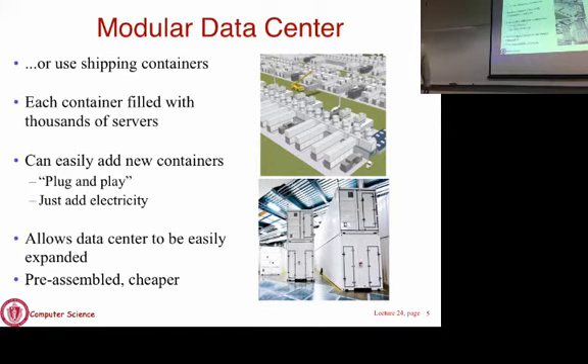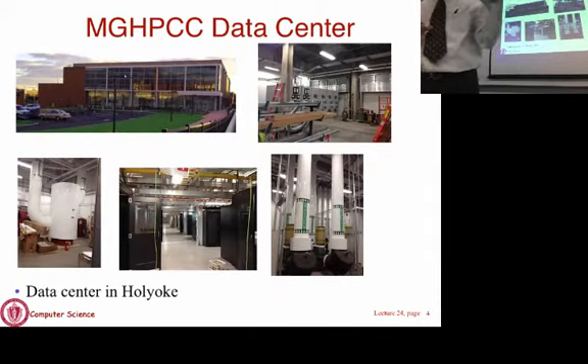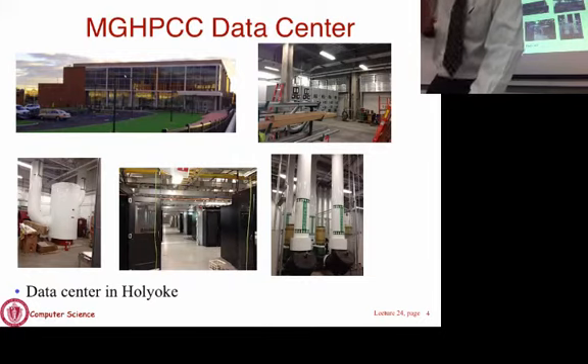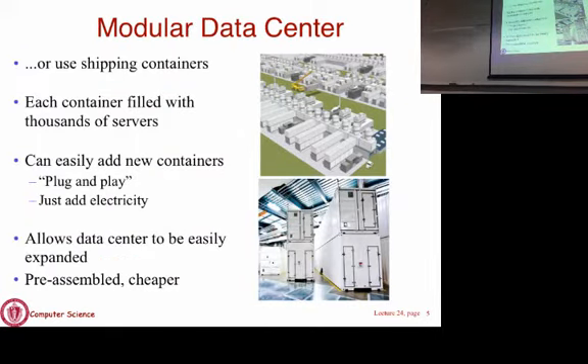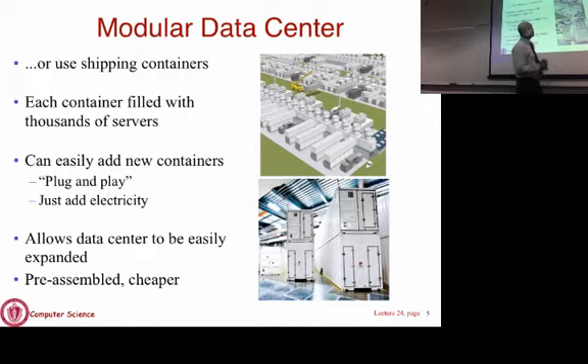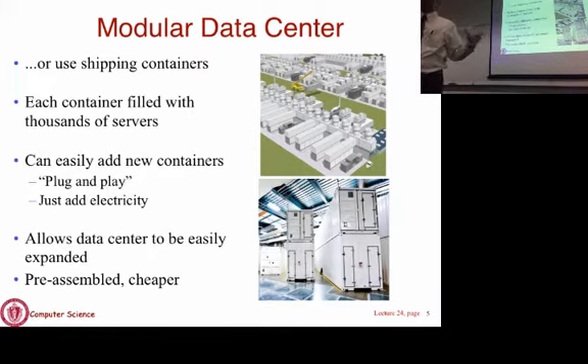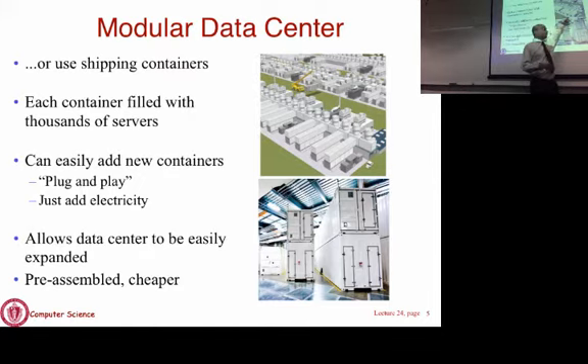That's one way to build a data center, but it's expensive. This facility cost 80 million dollars to build — not even counting the computers, just the shell, air conditioning, power infrastructure, and networking. So companies like Microsoft and Google have started building data centers in modular units. Rather than a warehouse, computers sit in shipping containers — 40-foot containers — that are self-contained units, pre-populated and cabled by the manufacturer.